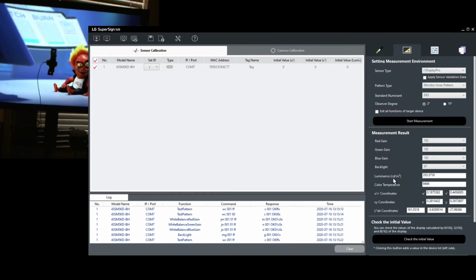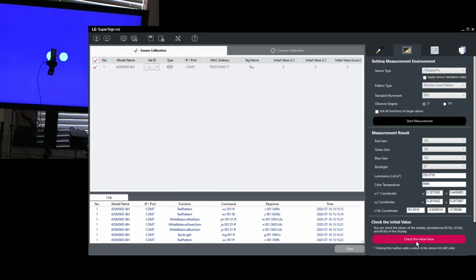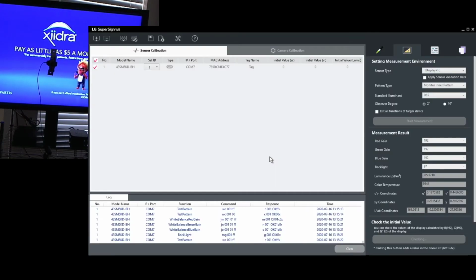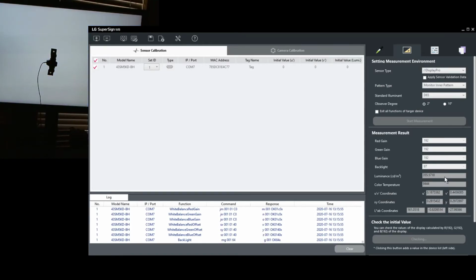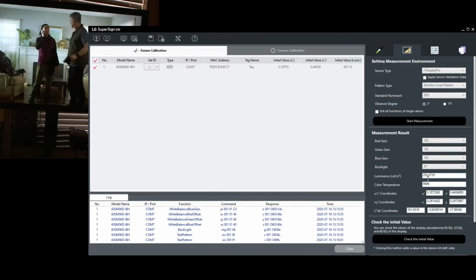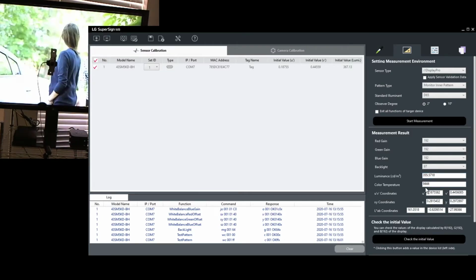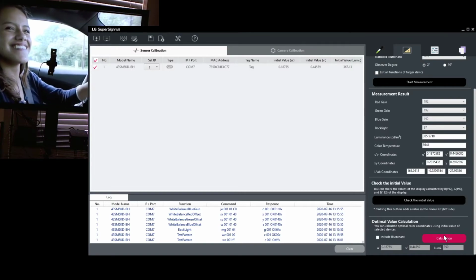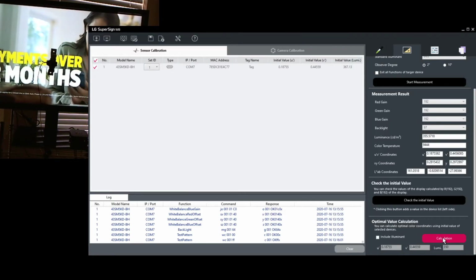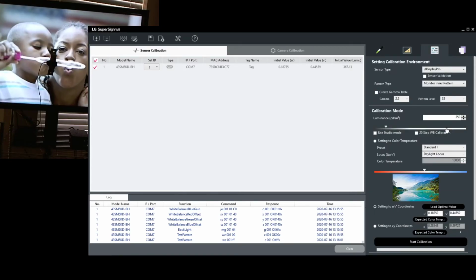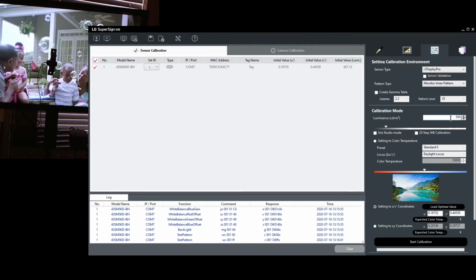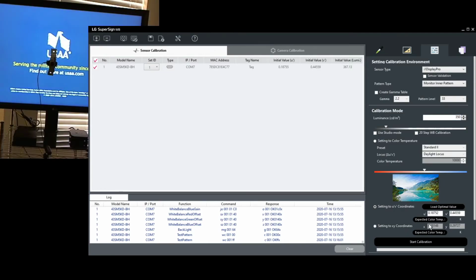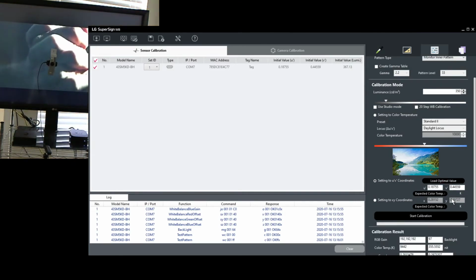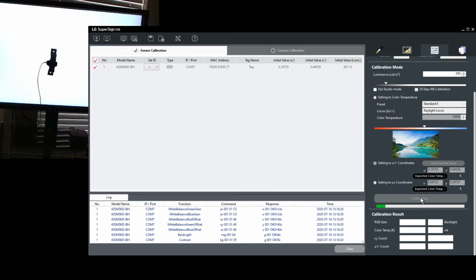Okay. So we can continue on this process, and we could check the initial value once again. We'll go through this process over the RS232 to see what kind of variations we get in the actual calibration. So remember, we're at 355.5718 on luminance and color temperatures at 9444. Let's do that calculation. And so now let's go back to calibration, the calibration environment. Remember, we still want to set our luminance for 350. Optimal value, it did change, the value changed. So now let's start the calibration process again.